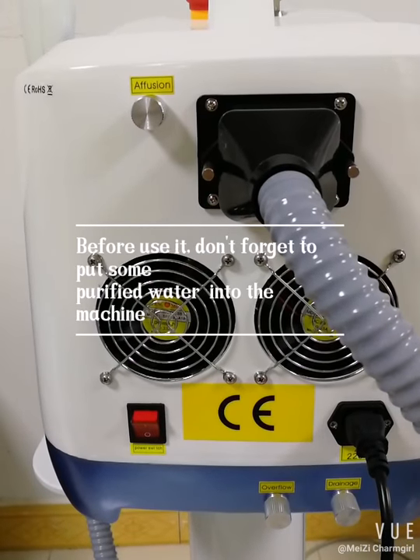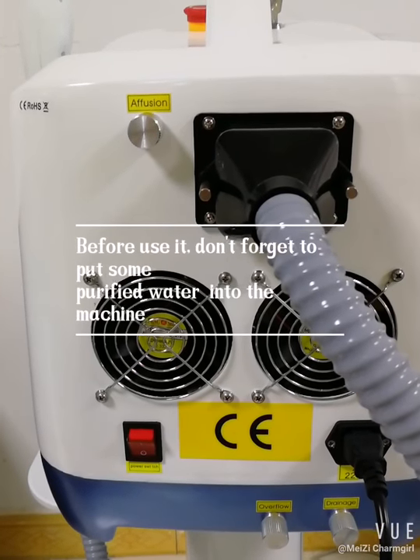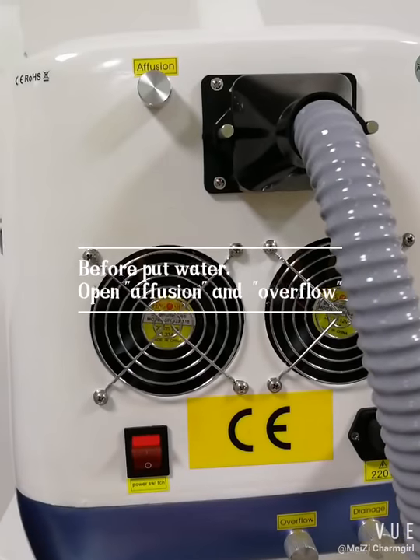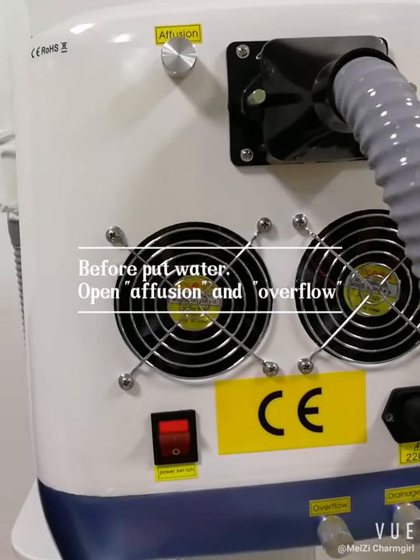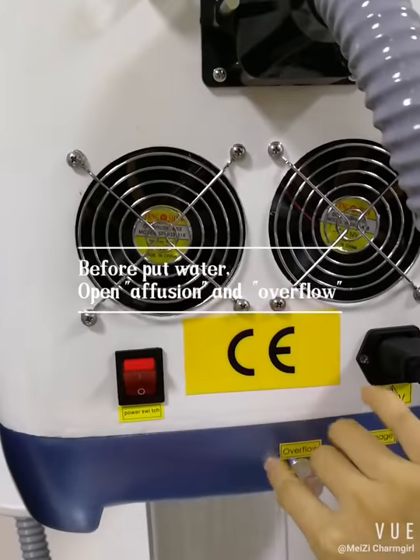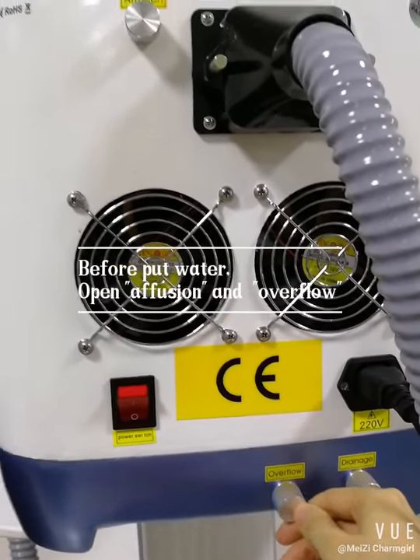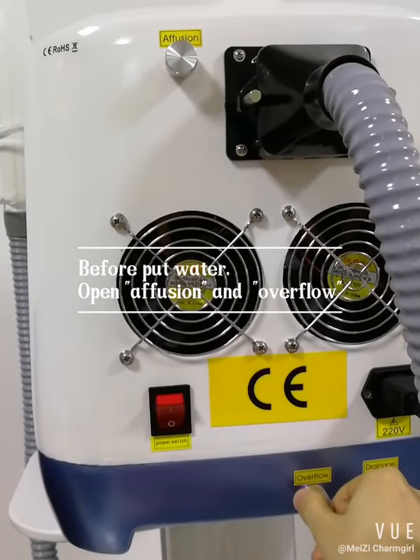Before we start using this machine, we should put some purified water into it. When putting purified water inside the machine, we need to open the affusion and also open the overflow. When water flows out from the overflow, that means the water level is enough.